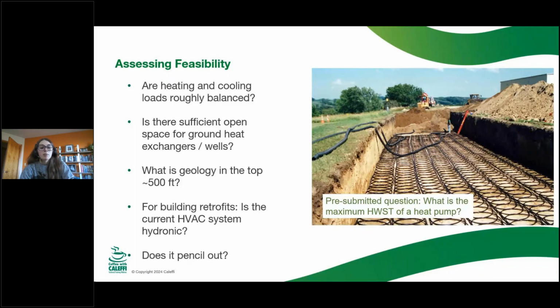I did get a pre-submitted question I wanted to touch on: what is the maximum hot water supply temperature of a heat pump? This is also important in a retrofit application. Heat pumps commercially available in the United States can get to about 140, maybe 160 degrees. There are some heat pumps in Europe I've been told can reach higher temperatures, using ammonia as the refrigerant. But commercially available in the United States, you're really looking at a maximum hot water supply temperature of about 140 degrees. So if you're looking at a retrofit application, and your hot water supply temperature is 180 degrees, you're probably going to have to redesign your heating coils, replace those, or look at installing a supplemental boiler to bump up that hot water supply temperature when temperatures outside are really cold.